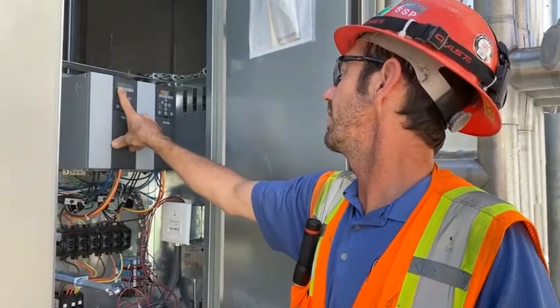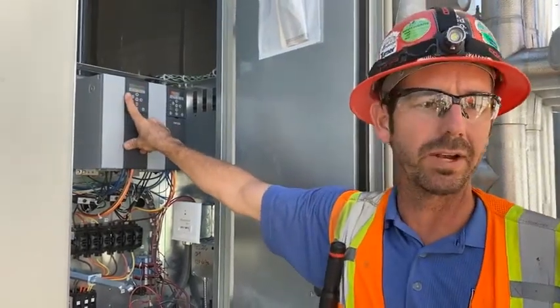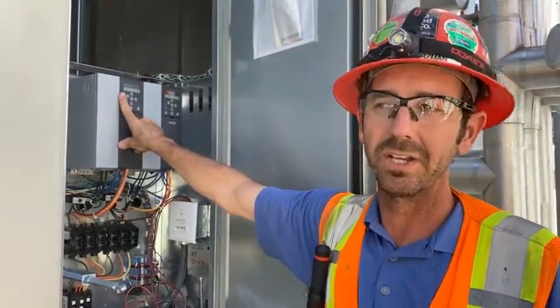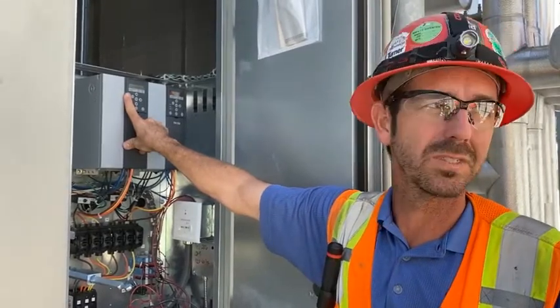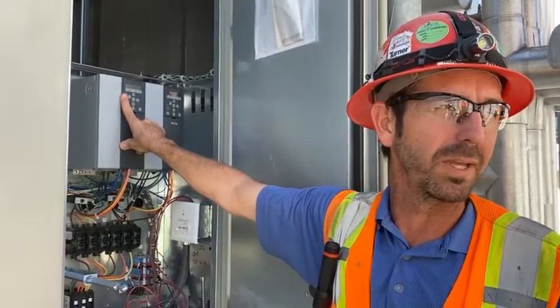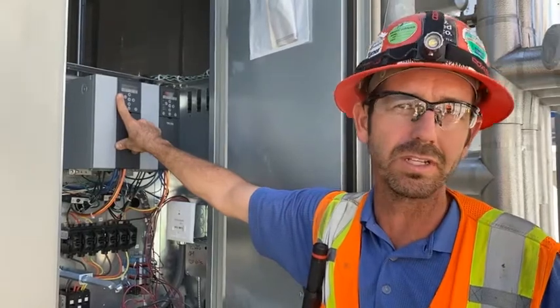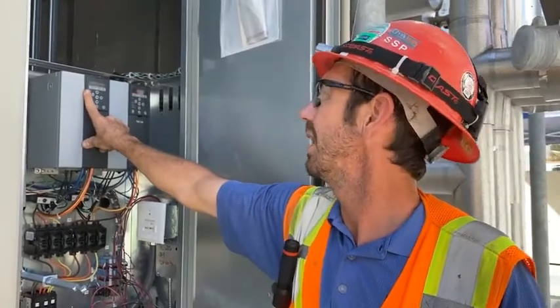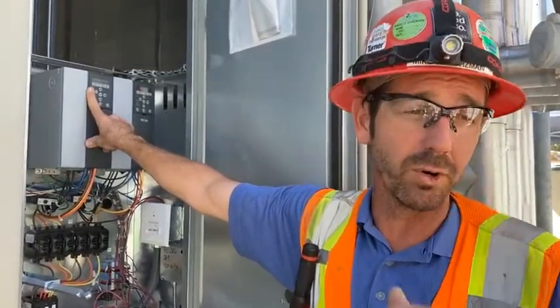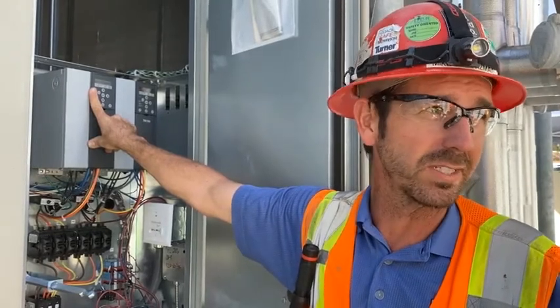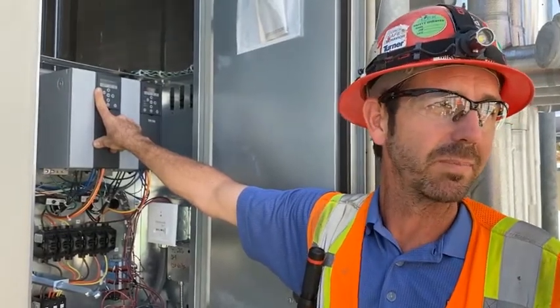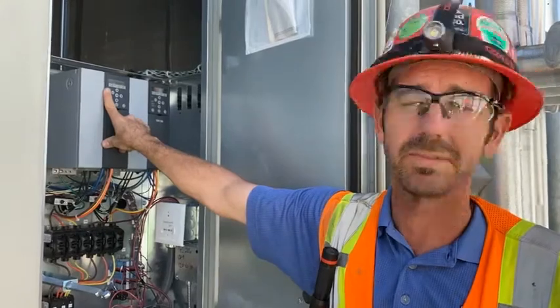This is a quick menu to get into the motor setup. When you get a replacement motor, you need to verify all the settings are the same. So you program volts, amps, RPM, verify the horsepower and the voltage of all those. Make sure you check all of them. Make sure you've ordered the right replacement drive. If it's a 460 drive, the power coming in needs to be 460, okay? It's important.